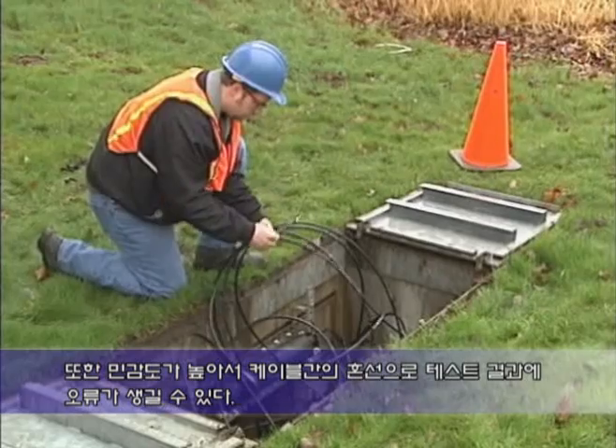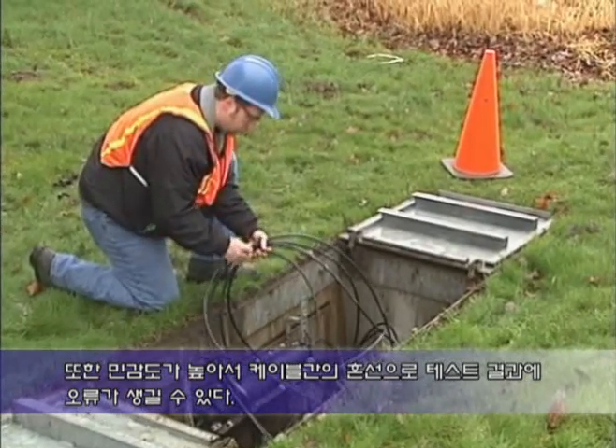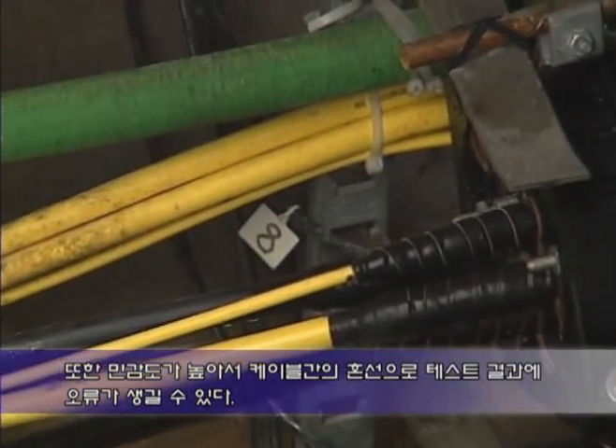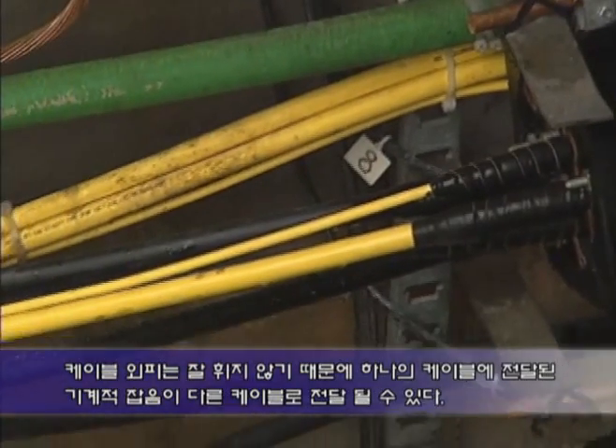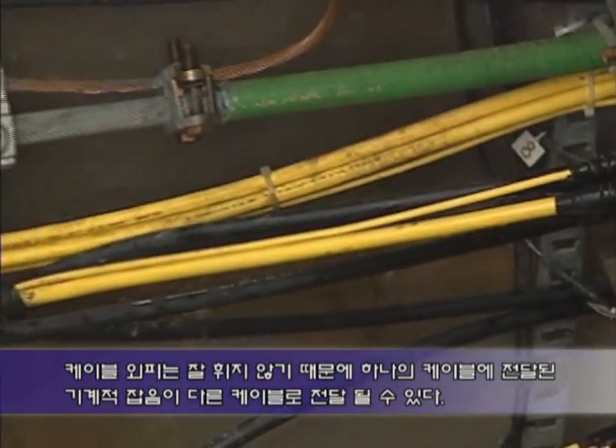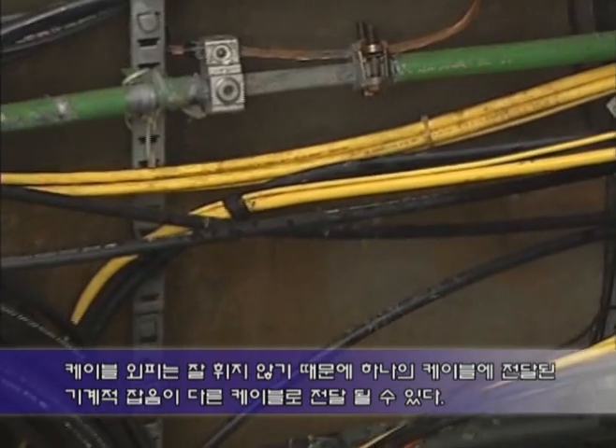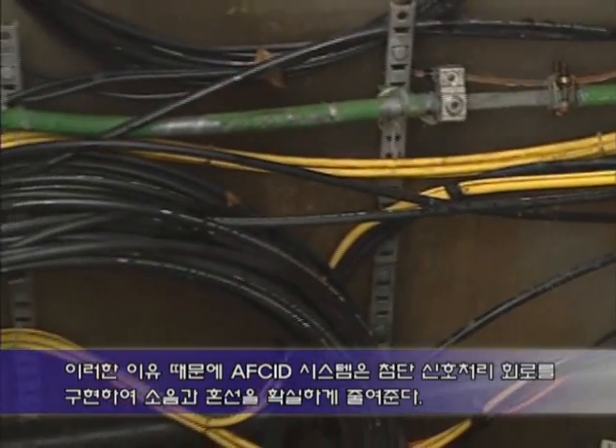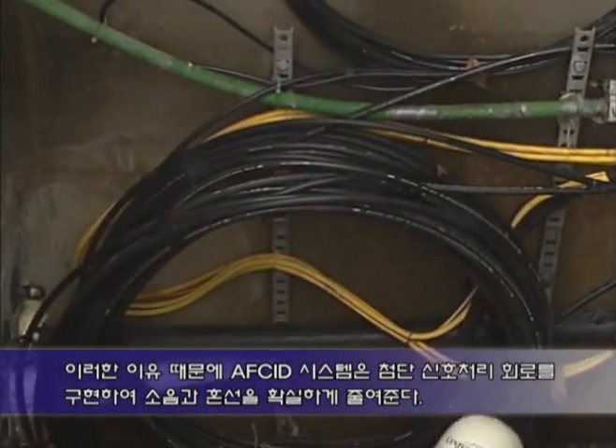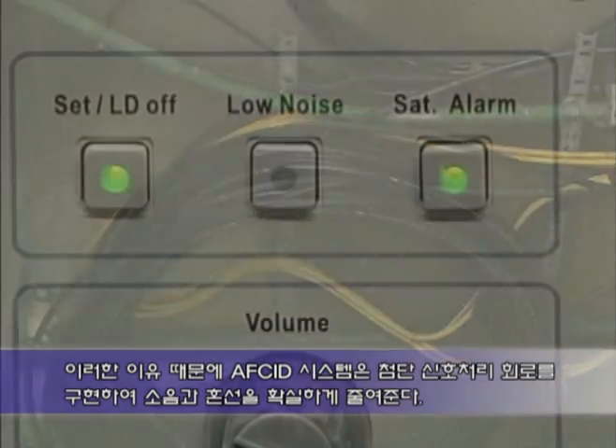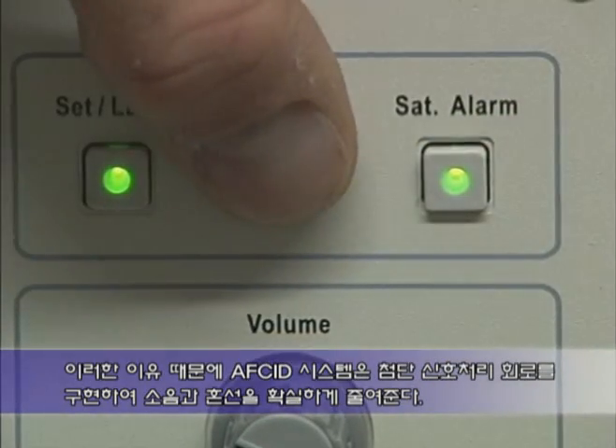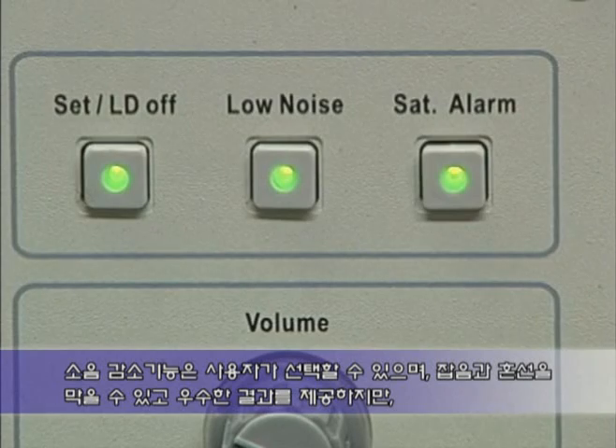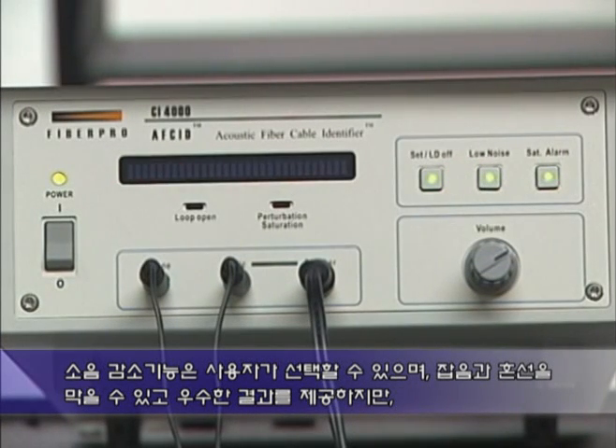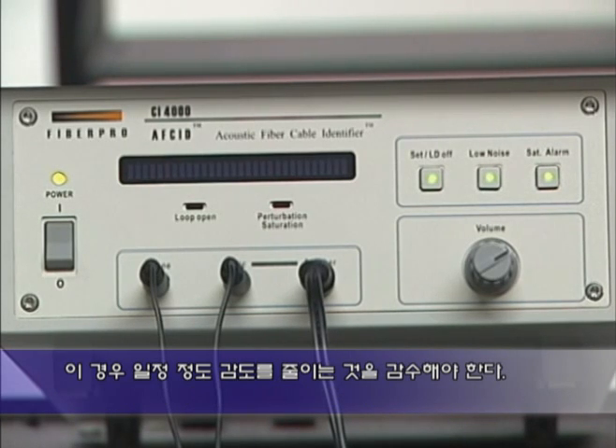In addition, high sensitivity can also allow crosstalk to produce false positive test results. Because cable jackets are rigid, mechanical disturbances introduced to one cable in a bundle can be coupled to the other cables. For this reason, the AFCID system incorporates advanced signal processing circuitry to drastically reduce noise and crosstalk. Noise reduction is user-selectable and provides excellent results as well as greater immunity to crosstalk, but at the expense of reduced sensitivity.